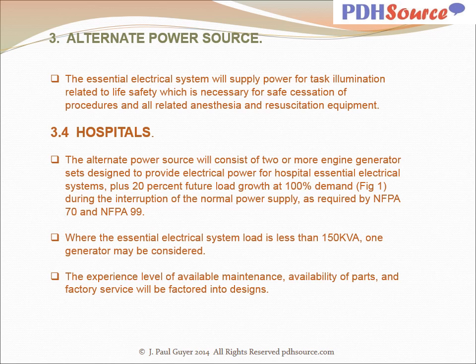With regard to hospitals, the alternative power source will consist of two or more engine generator sets designed to provide electrical power for hospital essential electrical systems plus 20% future load growth at 100% demand, refer to Figure 1, during the interruption of the normal power supply as required by NFPA 70 and 99. Where the essential electrical system load is less than 150 kVA, one generator may be considered. The experience level of available maintenance, availability of parts, and factory service will be factored into designs.